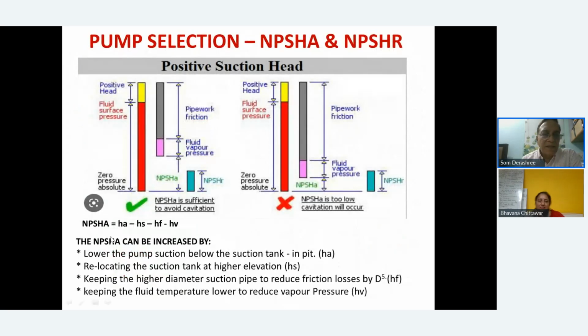So you see a typical case. You have a positive head. There is a myth also that if the tank is on top and the pump is at the bottom, cavitation will never happen. No, it can still happen. How? You have a positive head and a fluid pressure which is zero, absolute, here. Now, this is the pipe friction and this is the vapor pressure. So available is this much and required is up to this much. So there is still a gap. Available is more than what is required. This is NPSH available and this is NPSH required.